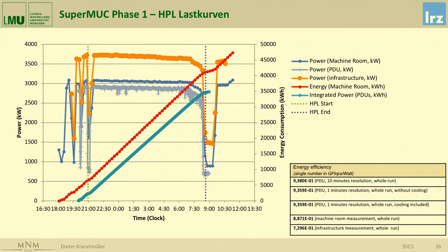And this is how the demand is - what happens if the demand is needed? You see the current consumption for one run of Linpack, started around 20 o'clock, running into 9 a.m. We start with only 800 kilowatts when the operating system is just running. When the job is started, it goes from 800 kilowatts to 3 megawatts. In addition there's also the cooling, so we need more than 3.5 megawatts.